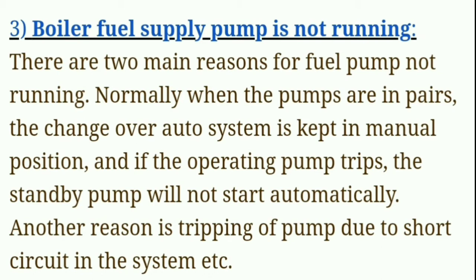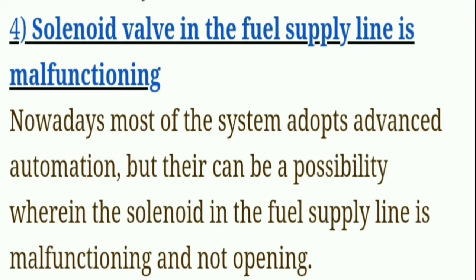Third, the boiler fuel supply pump is not running. There are two main reasons for the fuel pump not running. Normally, when the pumps are in pairs, the changeover auto system is kept in manual position, and if the operating pump trips, the standby pump will not start automatically. Another reason is tripping of the pump due to a short circuit in the system.